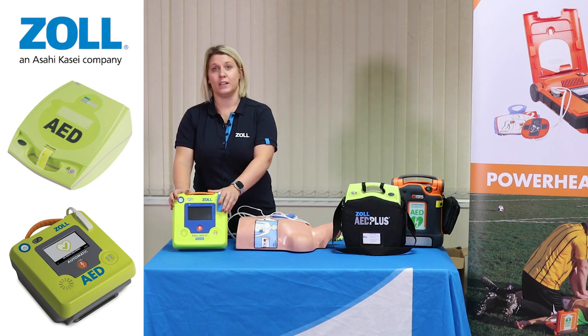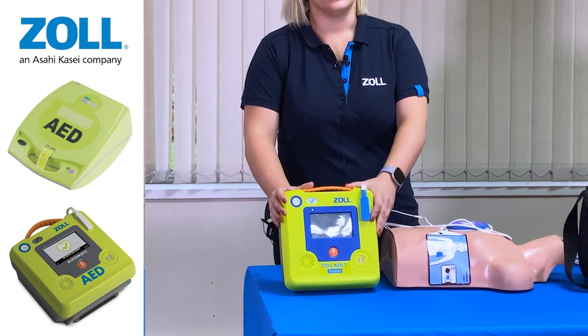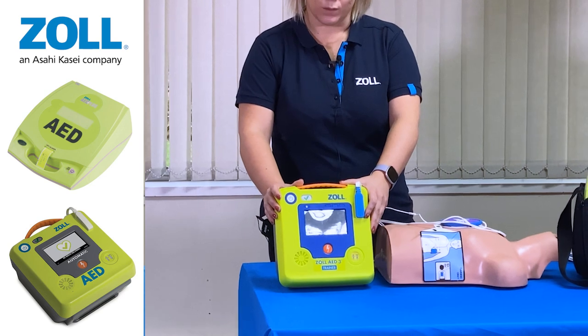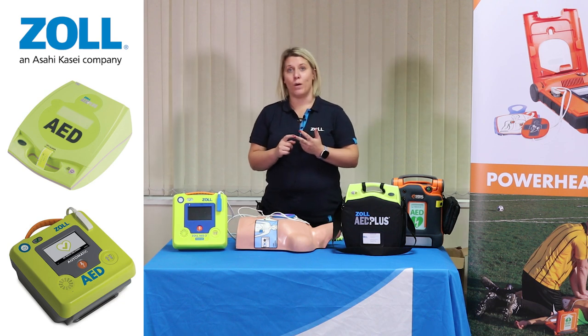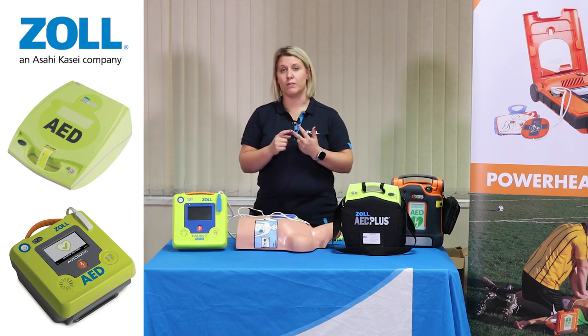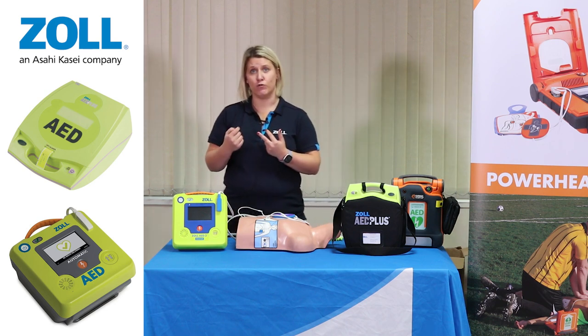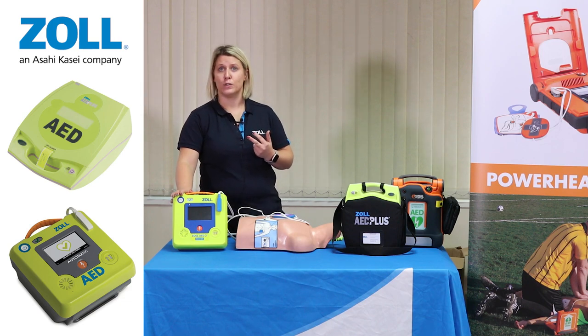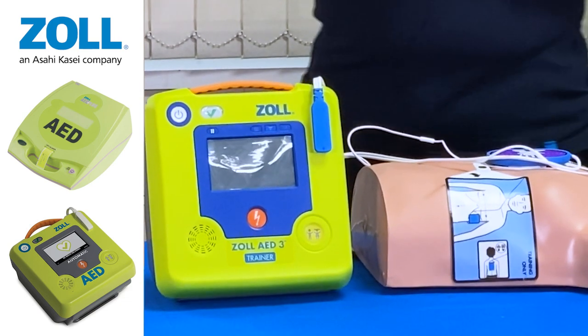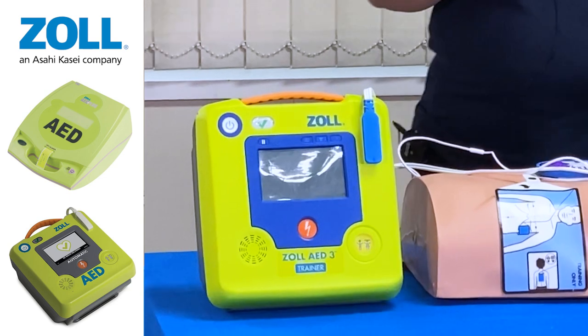What makes this even more advanced is that the device has Wi-Fi capability. It will allow you to use our program management system, which can be subscribed to, called PlusTrac, which will do three things for you. It will send reminders of when pads and batteries are due to be renewed. Research suggests 40% of devices in the community are not rescue ready at any given point, so having this service is really useful. Secondly, you can also see on a Google map exactly where the defibrillator is located, and you can input where it's located in the building as well.